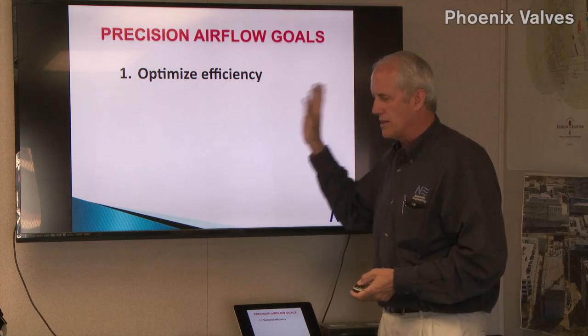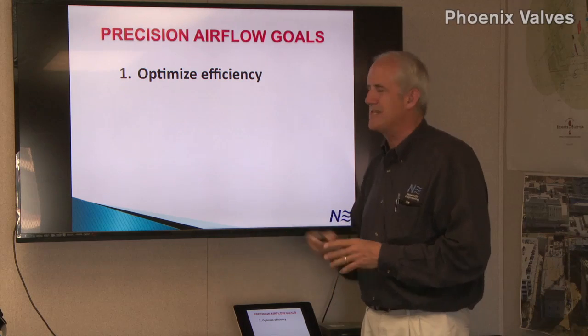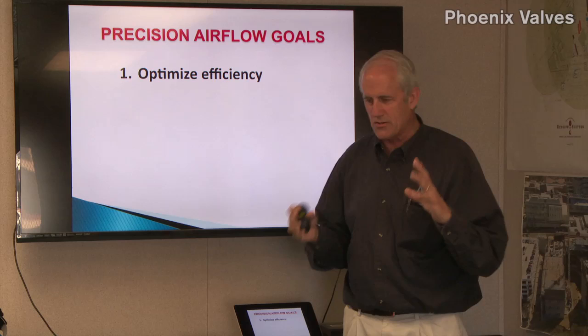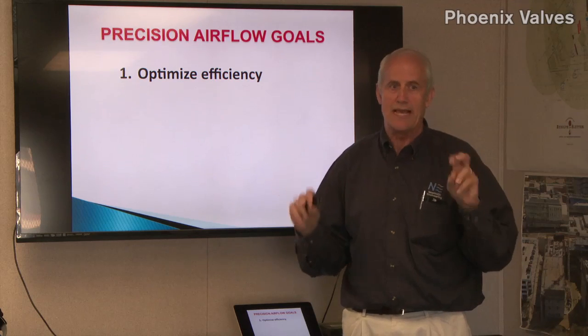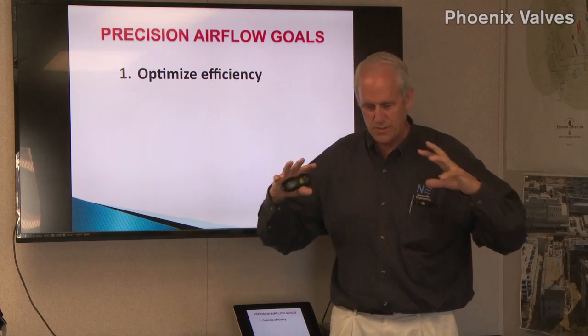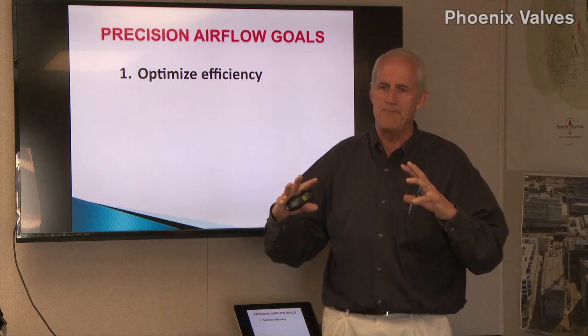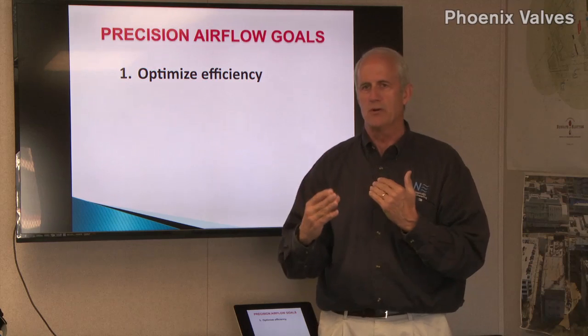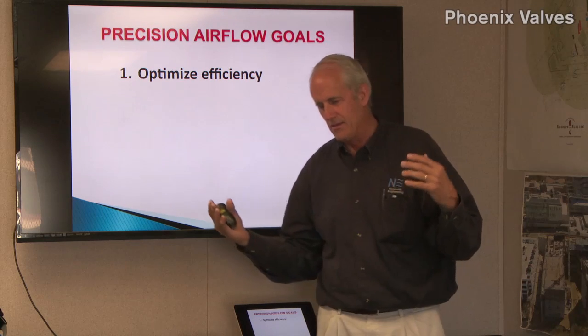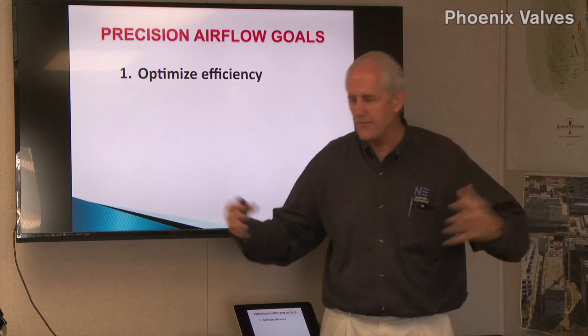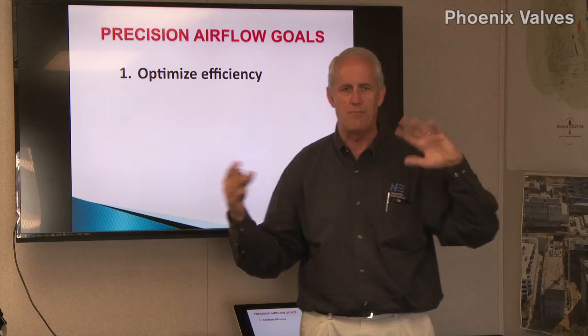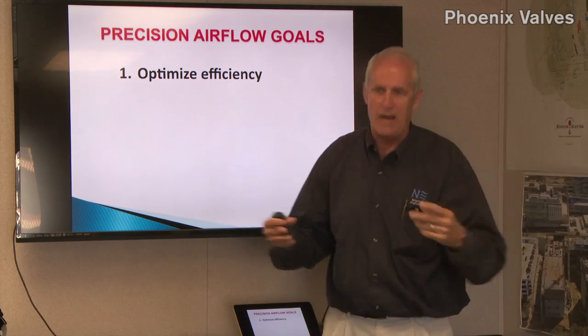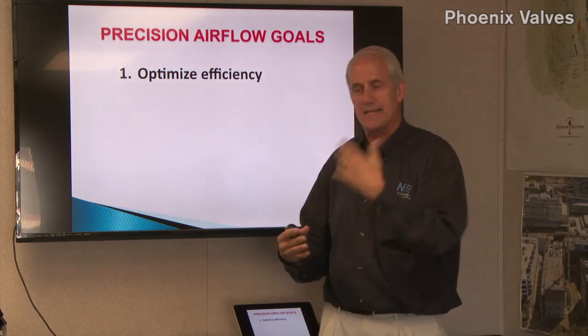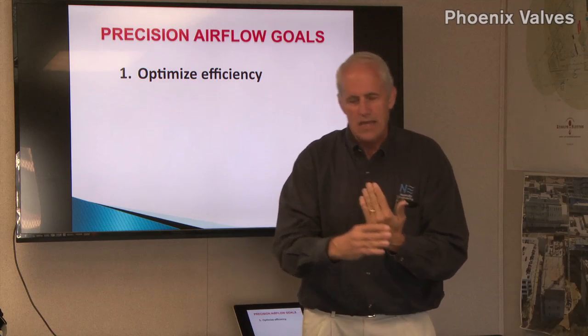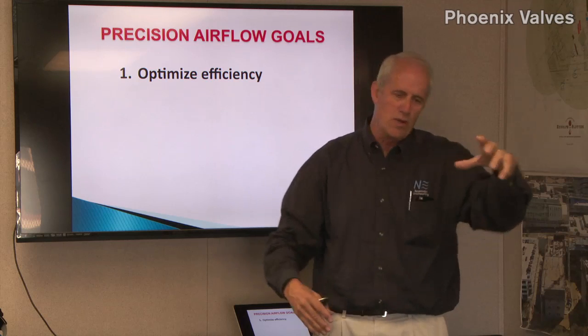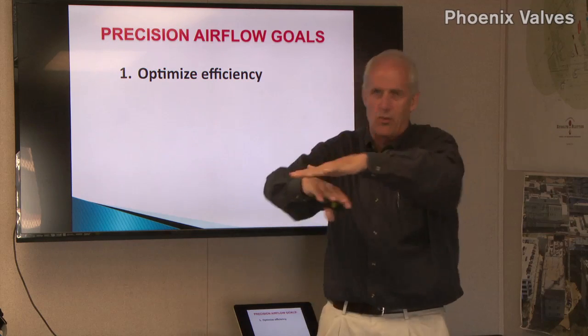So our goal is to make the system as efficient as possible, to optimize efficiency. In a vivarium, it's so critical. These vivariums are designed to be two-state. Basically, the rooms are operating constant volume most of the time, and then there's a switchable mode. So let's say the room is slightly positive because you've got some immune compromised critters in the room, and then there's an outbreak, so they want to flip it to negative. So you flip a switch, that's the two-state. We would flip to negative. When we flip to negative in the room, we would tell our corridor to give a little more supply air in order to balance the floor plate.